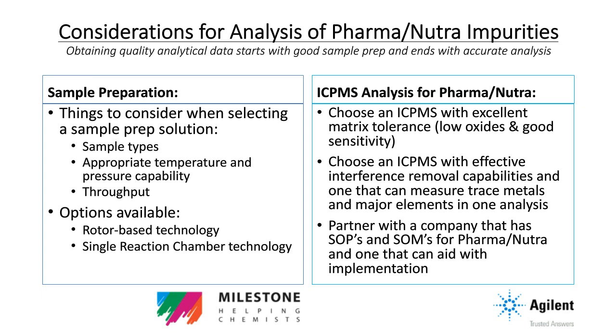The next question is: how to make sure that the tuning is done properly in ICP-MS? When you have an Agilent ICP-MS and you use one of our preset methods for USP, for example, the tuning criteria are already written into the software. All you would have to do is run one of the automatic tune report functions and the system would go to the tune solution, run a certain set of tests, and then it's bound to pass-fail criteria set in your tune report. On Agilent ICP-MS, it's all pretty heavily automated. If you have a different ICP-MS or you want to do it manually, with MassHunter there's a huge variety of openness of how you can set up your own tune criteria and make a pass or fail based on your own judgment.